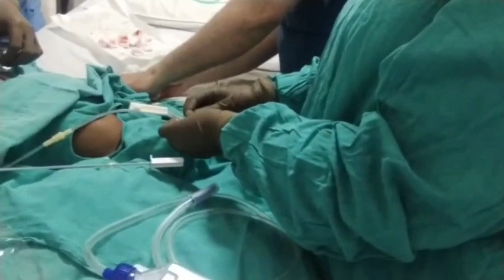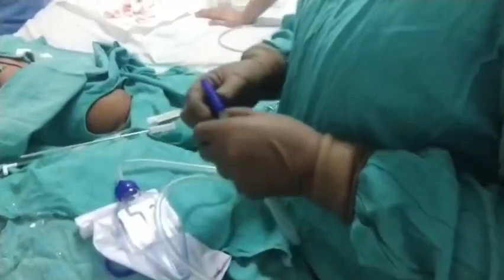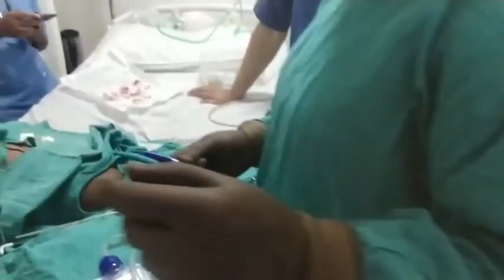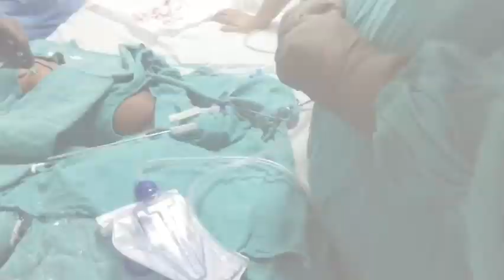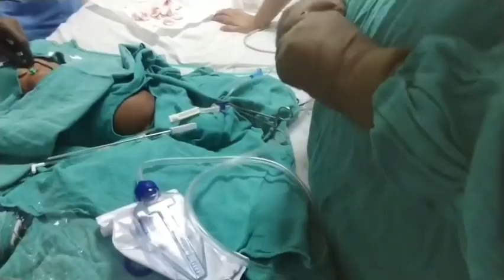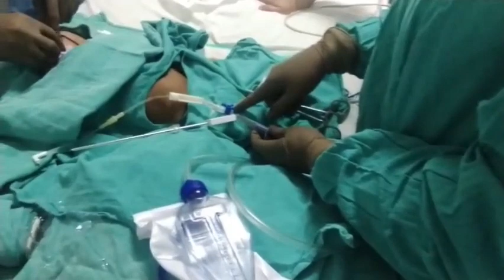So inlet is this one, from where the fluid is coming in, and this is the outlet. For connecting with a urometer so that you can measure the output of the PD fluid, you need to have a 2 ml syringe with which you can connect. So this has to be fixed. We have fixed this. Now you can see this can be connected here. Okay. So this is the whole connection. The PD fluid is coming in from this side, going inside like this, and then coming out from this side.